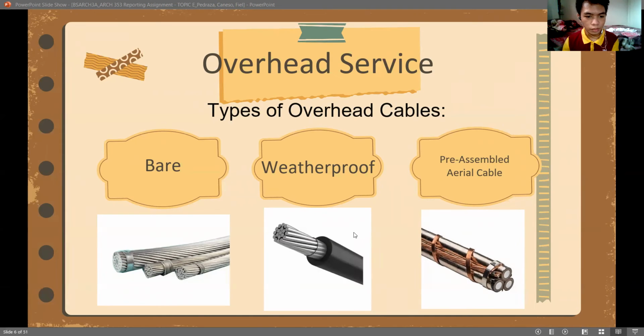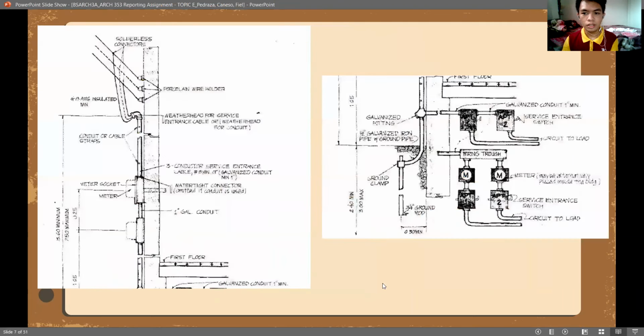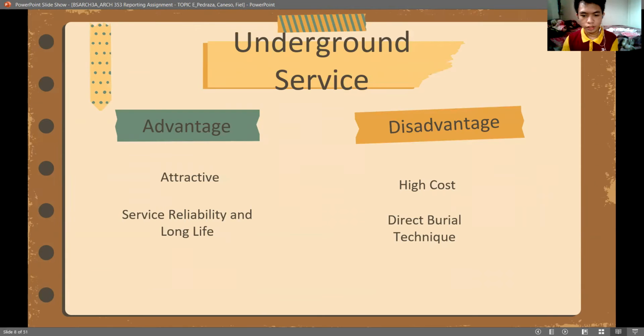Pre-assembled aerial cable consists of 3 or 4 insulated cables wrapped together with a metallic tape, as you can see here, and suspended by hooks from the poles. This type of construction may be used up to 15 kilovolts, and is more economical. So here is an example of an overhead service. Let's proceed to the underground service. So here are the advantages.